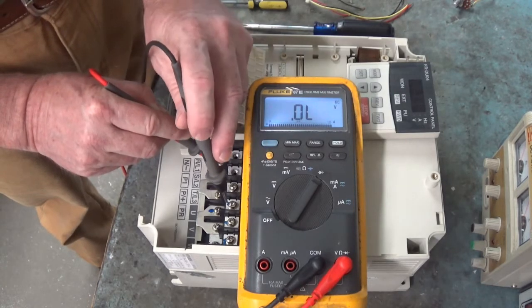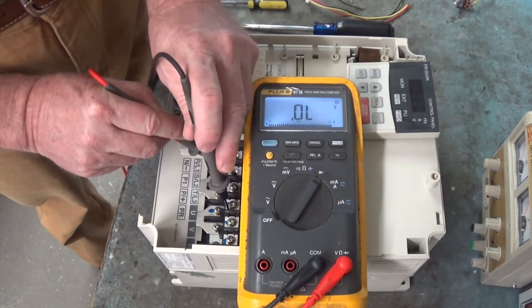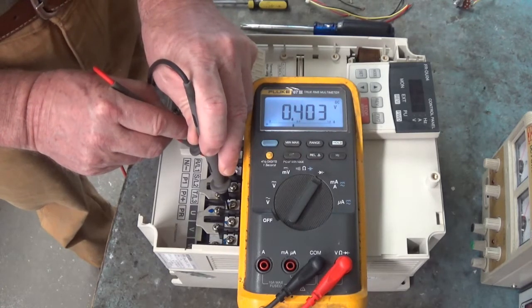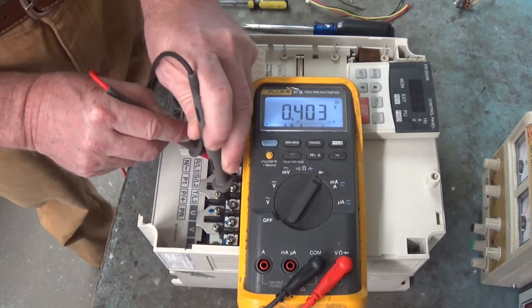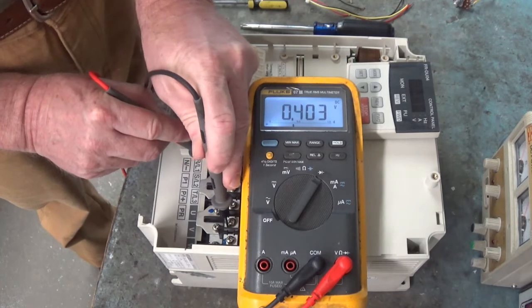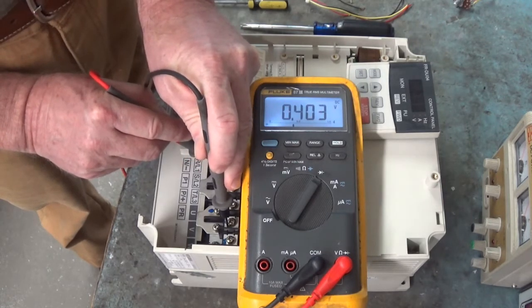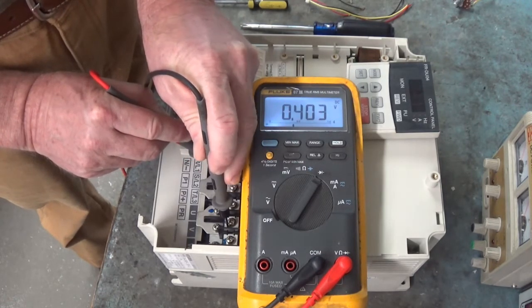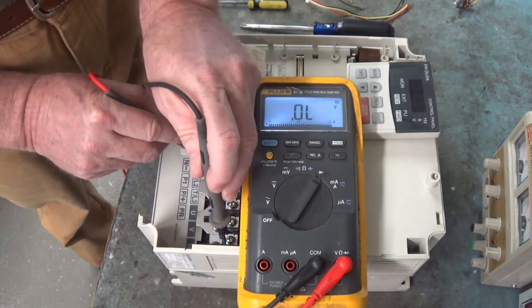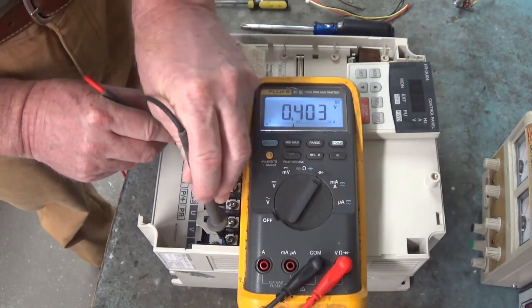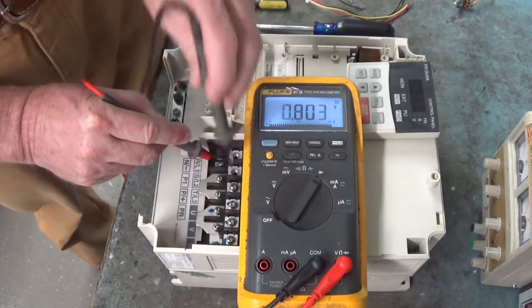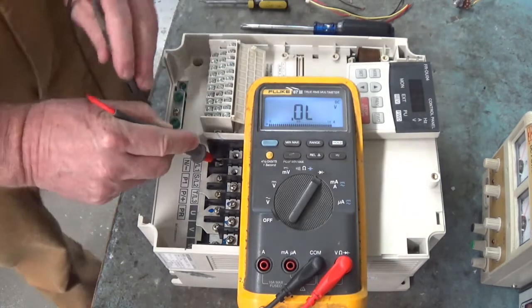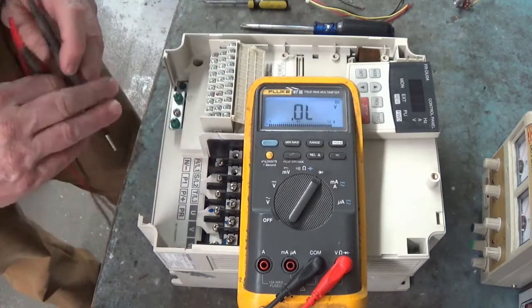Now let's look at the motor. Let's put our black lead on U. 0.403. That's good. Black lead on V. 0.403. That's good. Black lead to W. 0.403. And all that with keeping the red lead on N slash minus.